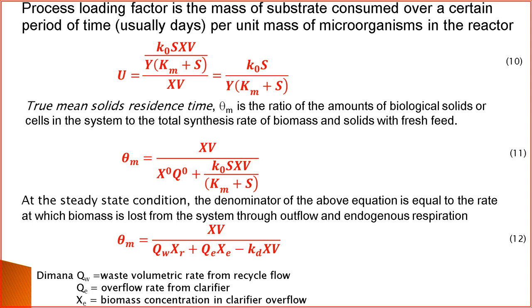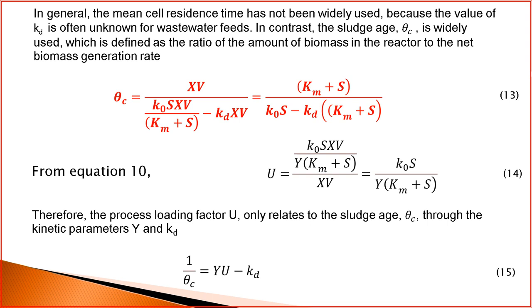Where Qw is the waste flow rate from the recycle stream, Qe is the overflow rate of the clarifier, and Xe is the concentration of biomass at the clarifier overflow. The term sludge age theta_c is defined as the ratio of biomass in the reactor to the net rate of biomass generation: theta_c = X·V / (k0·S·X·V / (Km + S) − kd·X·V) = (Km + S) / (k0·S − kd·(Km + S)).